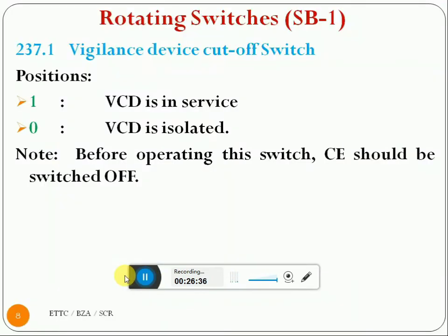Condition for operating this switch: CE off and change the position, then CE on. In one position, VCD in service; in 0, VCD isolated. Before operating this switch, CE should be switched off. PT fuse, potential transformer fuse. There are two types of fuse provided, one glass type or HRC type fuse.